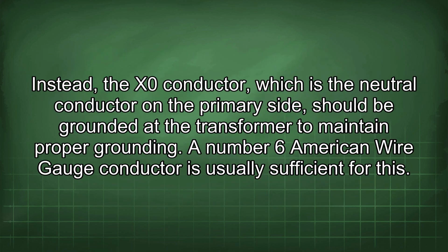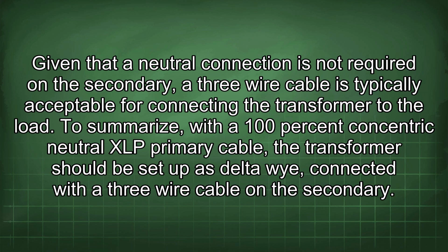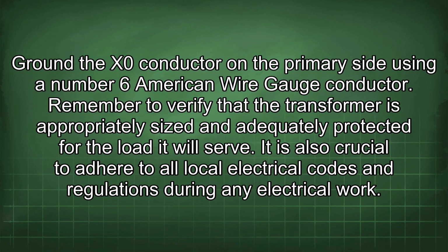Instead, the X0 conductor, which is the neutral conductor on the primary side, should be grounded at the transformer to maintain proper grounding. A number 6 American wire gauge conductor is usually sufficient for this. Given that a neutral connection is not required on the secondary, a 3-wire cable is typically acceptable for connecting the transformer to the load. To summarize, with a 100% concentric neutral XLP primary cable, the transformer should be set up as Delta-Wye, connected with a 3-wire cable on the secondary. Ground the X0 conductor on the primary side using a number 6 American wire gauge conductor.